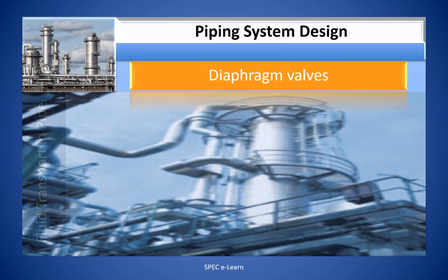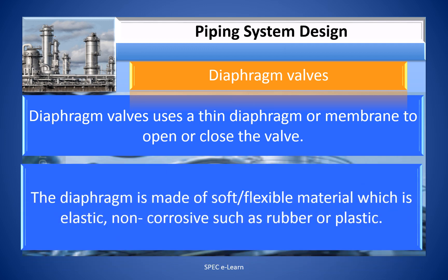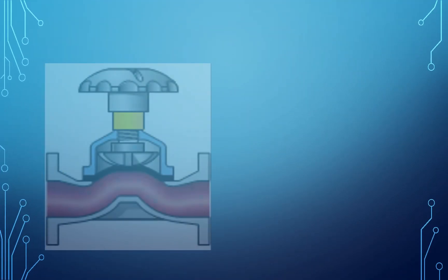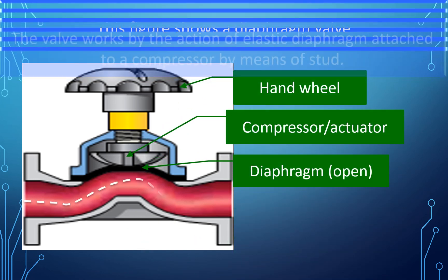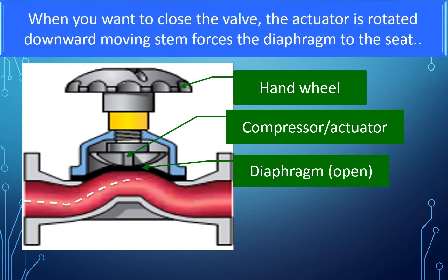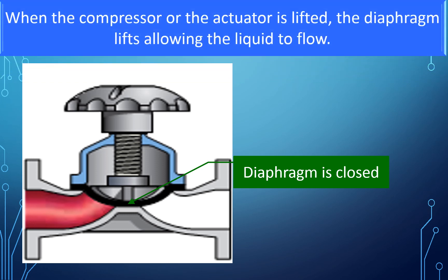Diaphragm valves use a thin diaphragm or membrane to open or close the valve. The diaphragm is made of soft, flexible, elastic, non-corrosive material such as rubber or plastic. The valve works by the action of an elastic diaphragm attached to a compressor by means of a stud. When you want to close the valve, the compressor or actuator is rotated or pressed, and the downward moving stem forces the diaphragm to the seat. When the compressor or actuator is lifted, the diaphragm lifts, allowing the liquid to flow.